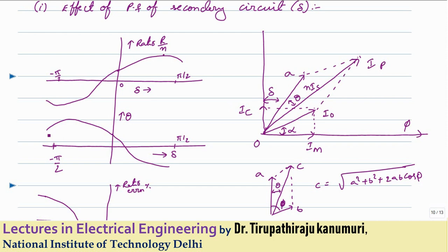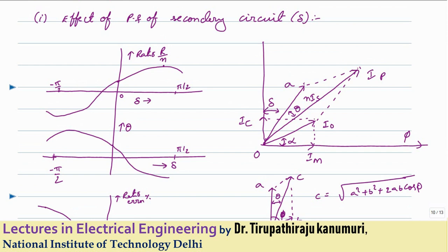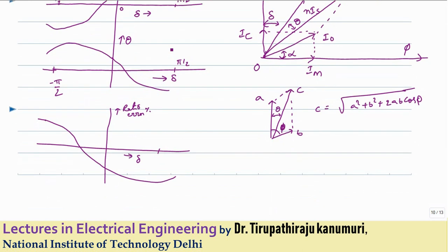We can conclude: as the secondary load power factor is lagging and the power factor increases, the ratio error magnitude increases, whereas the phase angle error decreases, reaching zero and then going negative. Conversely, as delta decreases (leading power factor), the phase angle error increases while ratio error decreases, eventually reaching zero. This is the combined effect of secondary power factor on both ratio error and phase angle error.